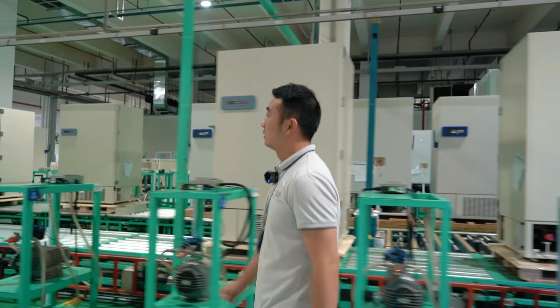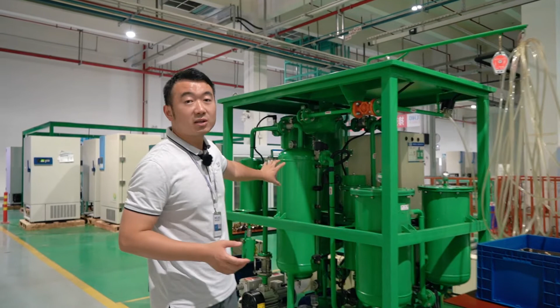After that, we will give back the POE oil to these compressors. This is the heating equipment. After we get these compressors from our suppliers, we will take the oil out in case of moisture content, fill this oil inside the heating equipment and do the heating to volatilize this moisture, then charge this POE oil back to the compressor.